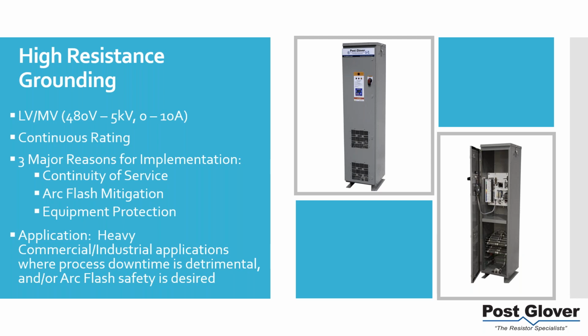So the point is, IEEE states that on a ground fault, which is about 98% of all your faults, you have 0% chance of an arc event on a high resistance ground system. So just to review: low voltage, ground fault, 98% of the time, no chance of arc fault. I did a previous presentation on NEC, or I should say IEEE says that, and I think I covered that in that presentation. The last one is equipment protection.